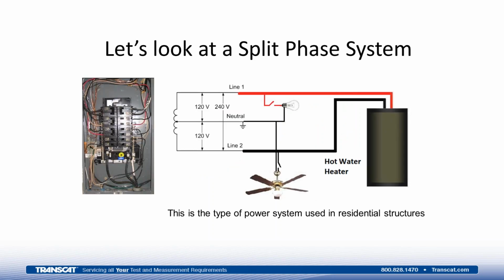More commonly used would not be a single-phase system. It would typically be a split-phase system. In this particular case, the transformer is now shown kind of to the left of this drawing. The transformer has the ability to have 120 volts from either phase to the center of the transformer. We typically would attach our neutral wire to the center of the transformer, and I would monitor 120 volts from either phase. We're not going to get into exactly how this works, but these two phases would be opposing each other. They would be 180 degrees apart, and as a result, we would have 240 across the transformer, or two individual 120 volt sources that are out of phase with each other.